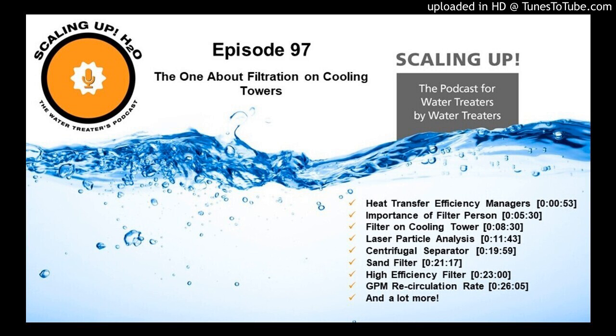It's very short term, a few days, where these particles, when they go into the cooling system and hit the heat transfer surfaces, reduce heat transfer, and you can cut many, many thousands of dollars a year in electrical use. Increased electrical use is what happens when you have particle loading. So I keep bringing my customers back to, yeah, we want to reduce the maintenance, but the key is you're going to save a lot of money with the electrical load changes and improvements. I have a lot of data and sheets on that people can look at too. I can provide all of that.